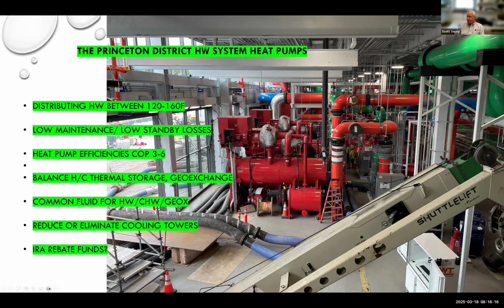We send out 43 degrees plus or minus chilled water, and we typically send out 140-degree water for heating. We can send out 160-degree water on the coldest days if we must, knowing that we can sacrifice COP for these few hours a year. And as buildings get more efficient, and as we find and correct local issues, we aspire to send out 125-degree heating water. So all our conversion designs are based on new heat exchangers inside the buildings that can produce 120-degree secondary water from 125-degree primary hot water. All the equipment inside the building then will work on 120-degree water.